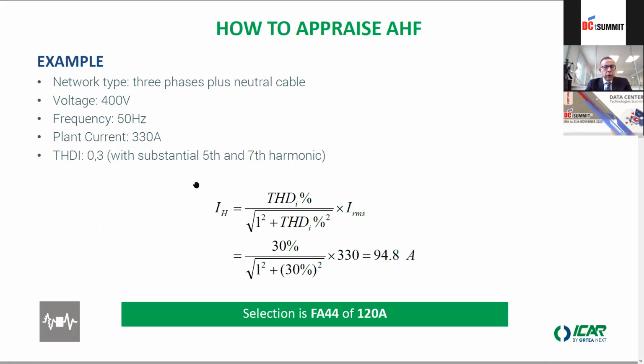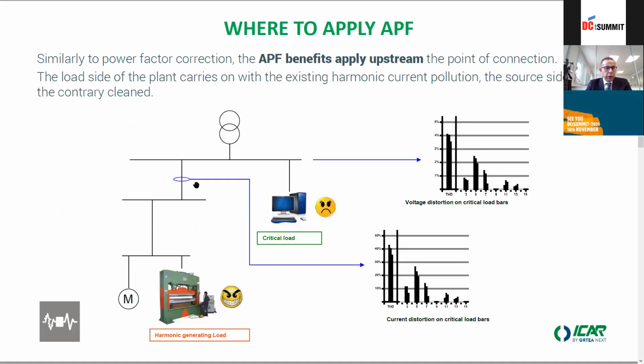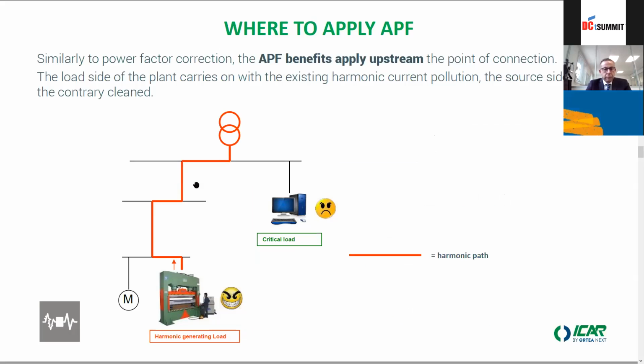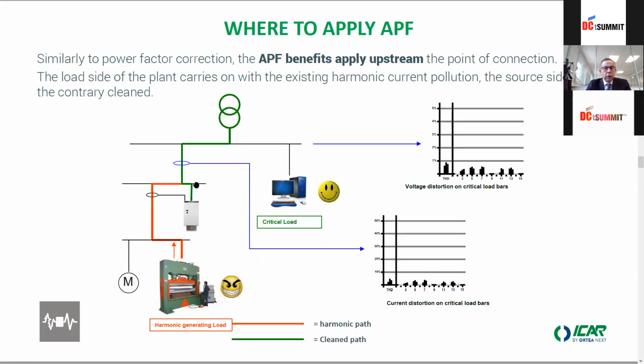Well, here there is a formula of how to make an evaluation of the real value of a harmonic for an active filter. Where to position an active filter is very important, because it's important to put it in the right position in the main line to avoid troubles. Otherwise, you will have the opposite solution. Here you can see that the position of a harmonic active filter is very important to have very high benefits and to avoid the problems. So you can see how is the circulation of the harmonics inside the line.